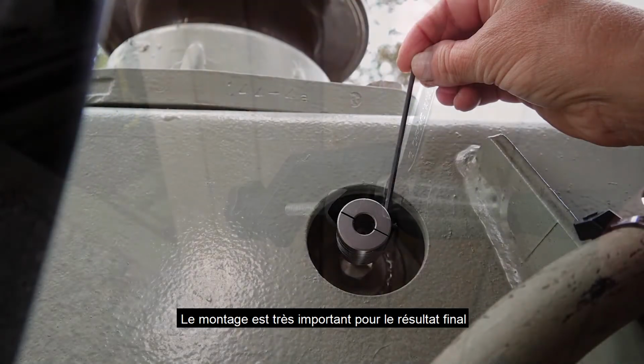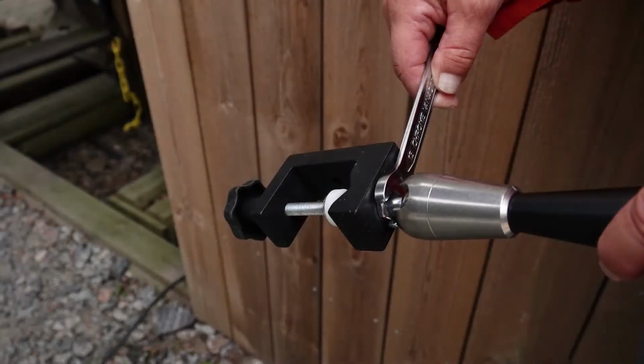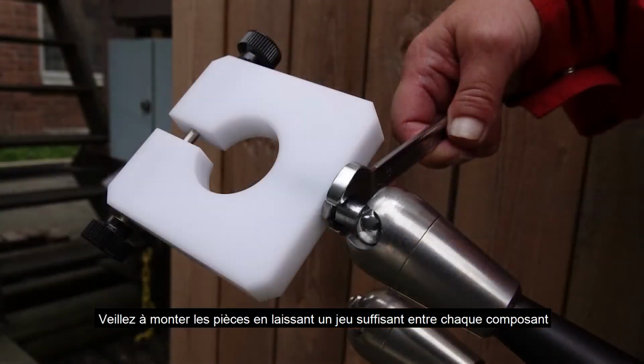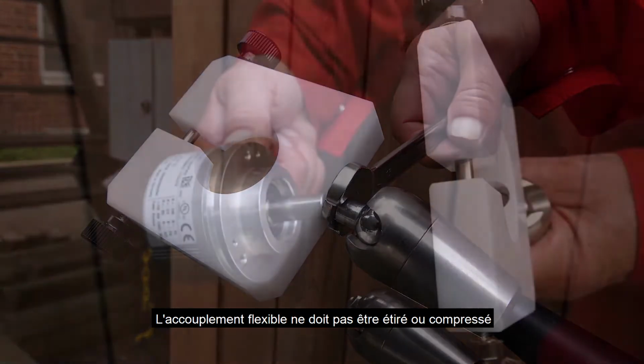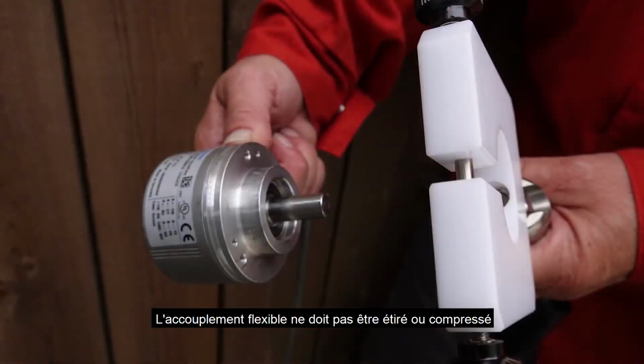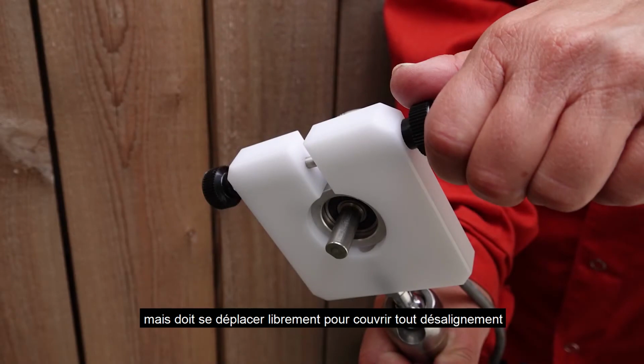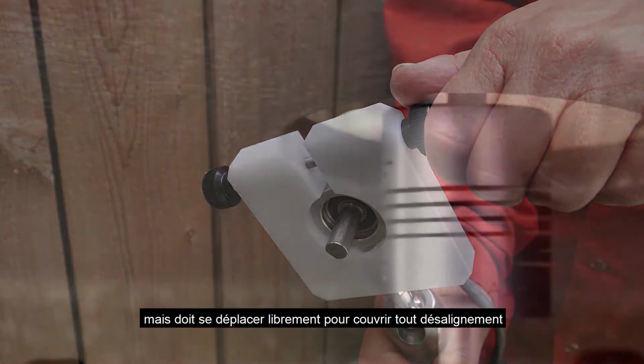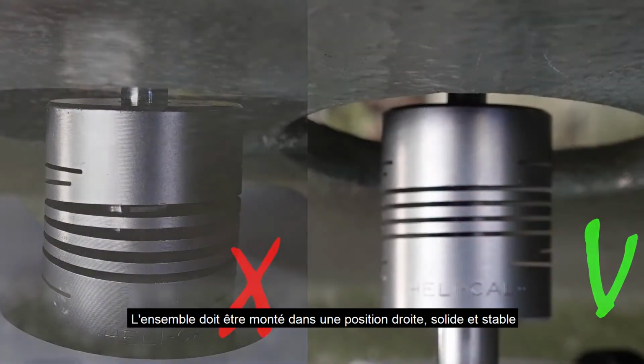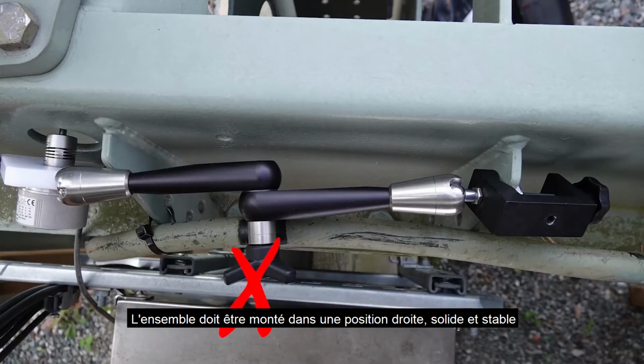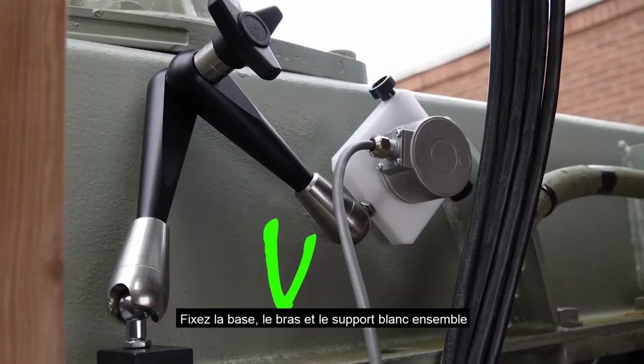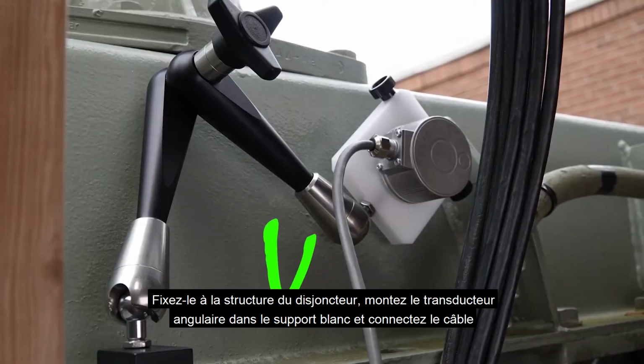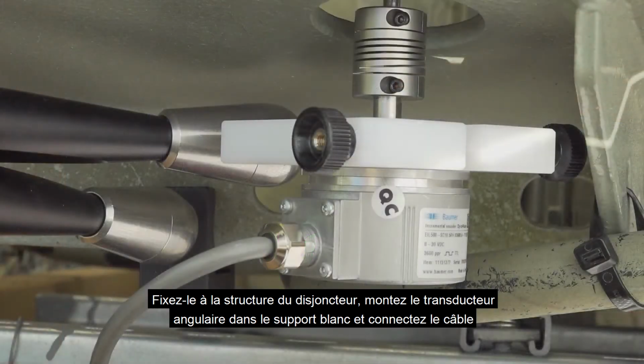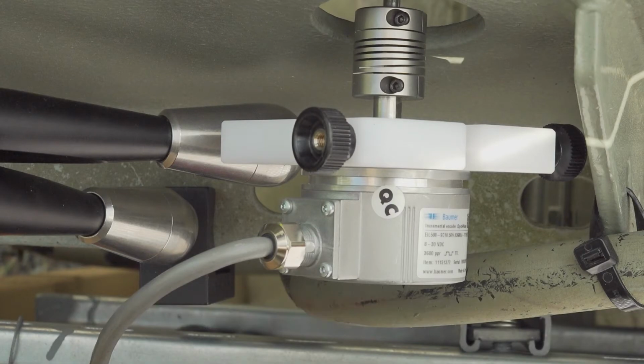The mounting is very important for the final result. Make sure you mount the parts with space between each component. The flex coupler must not be stretched or pressed, but needs to move freely to cover any misalignment. The whole setup must be mounted in a straight, strong and steady position. Attach the base, arm and white holder together. Attach it to the structure of the circuit breaker. Mount angle transducer in the white holder and connect the cable.